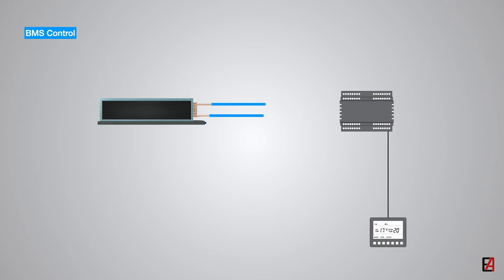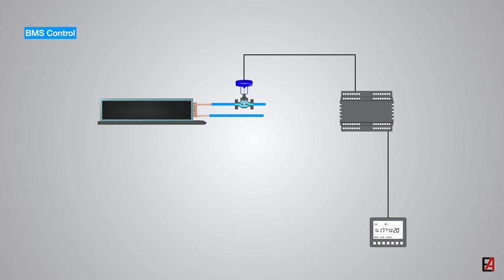The FCU controller reads the space temperature and modulates the control valve via a PID controller. The PID controller output will decide how much the control valve should be opened or closed in order to achieve the desired space temperature setpoint. If the space temperature is more than the setpoint, then the control valve will be fully opened, and when the space temperature is less than the setpoint, then the control valve will be fully closed based on PID output.